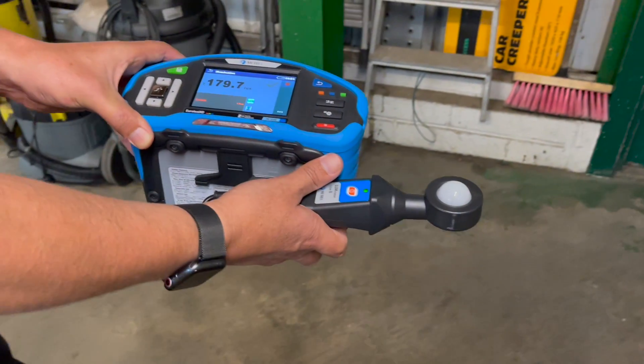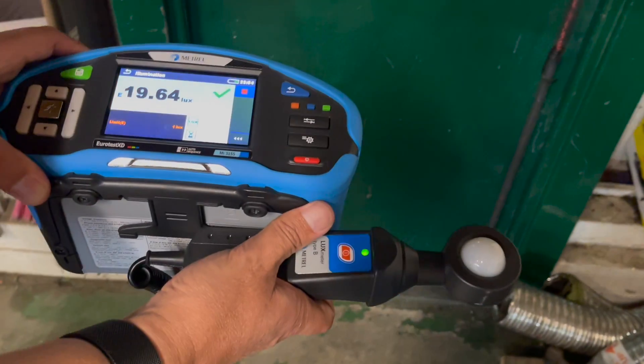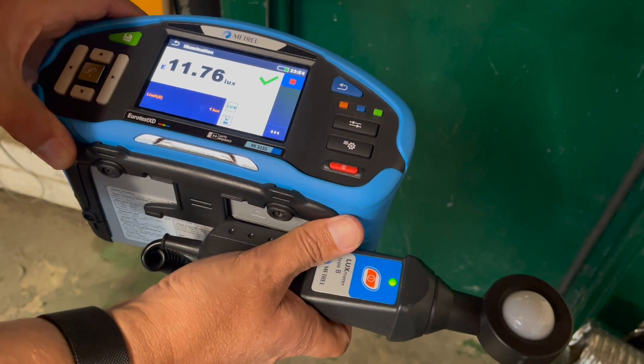While Ross and Gary crack on with the installation, let's look at the design process. We surveyed the workshop a few weeks ago and found two major problems. Firstly, the light levels are really low, with an average light level at floor level of around 70 lux — that's 10 times less than the typical levels recommended for this kind of application. The second issue is uniformity — the difference between the brightest areas and the dullest parts. We found areas as low as 20 lux.